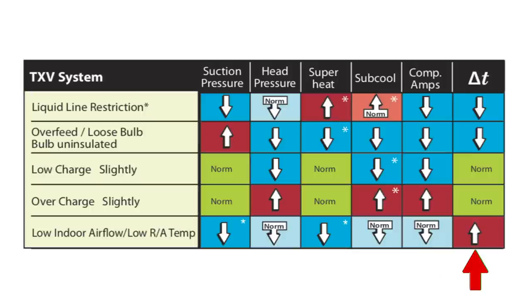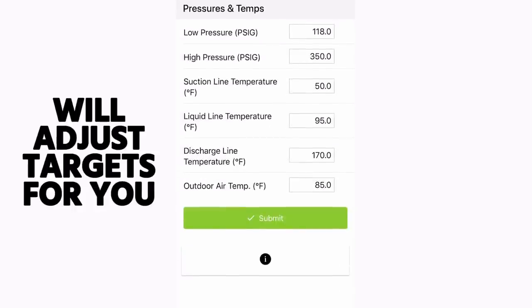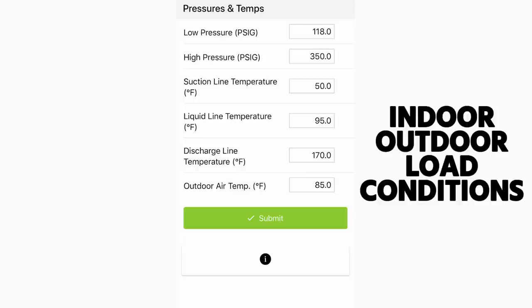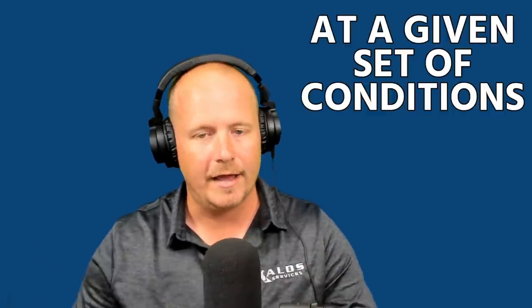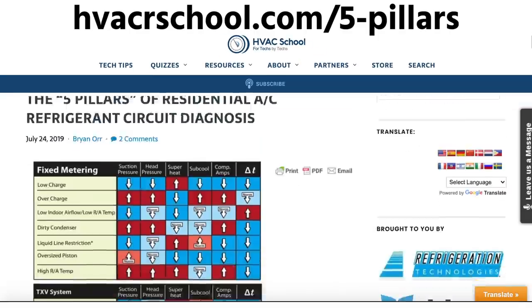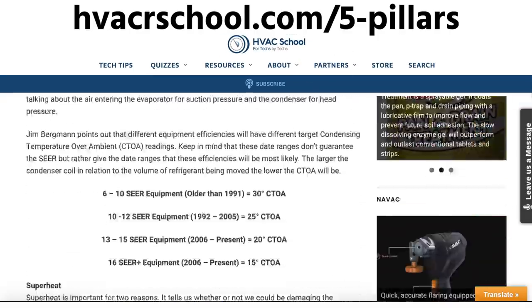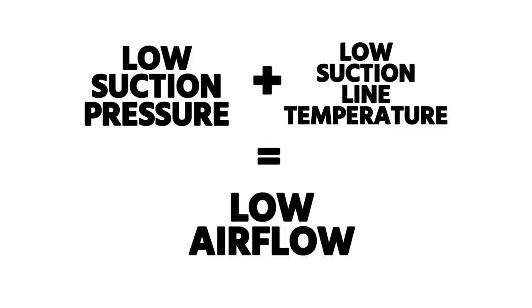Your delta T is going to be high. The MeasureQuick app will adjust those targets for your indoor and outdoor load conditions, making the targets much more accurate. One of the big things we face in the industry is people using fixed targets — saying suction pressure should be this number — but your suction pressure is only going to hit that at a given set of conditions. That's why you need to know the five pillars article and terms like CTOA, DTD, delta T, superheat, and subcool. Even without knowing all of that, you still learn that low suction pressure with low suction line temperature indicates low airflow.